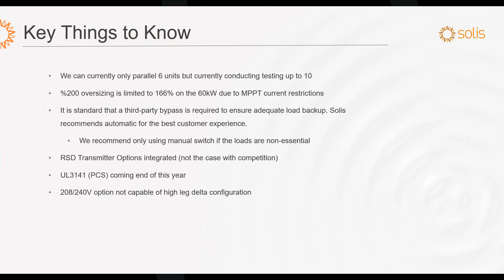The 208/240 volt option is not capable of the high leg delta configuration. This is not the case with our grid-tied commercial products that are 208/240, which are capable of high leg delta. We wanted to ensure you understood that because of the hybrid topology, we're not capable of the high leg delta configuration.